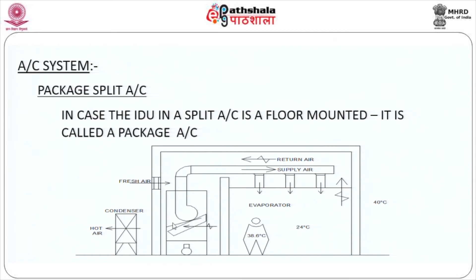A packaged air conditioner is basically like a split air conditioner, and schematically this would look like this. This would be the envelope of the air conditioned space. You will have a small room earmarked for this. You might call it an air handling unit room. In this air handling unit, the package unit is kept, a small quantity of fresh air is drawn into this room, and air is recirculated from the air conditioned space through a void over the false ceiling and comes back to the air conditioner. So basically again you have your evaporator, you have your condenser, and the link between the two, the compressor, has now been installed here itself, so that it's more protected from atmosphere. In other words, the three friends, the evaporator, the condenser and the compressor, are still required. They are still there, maybe in a different format, but without them there will be no air conditioning.